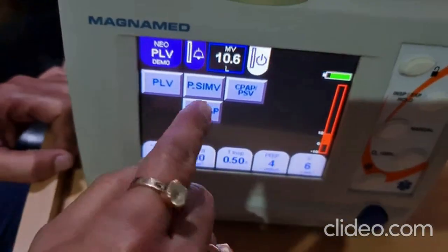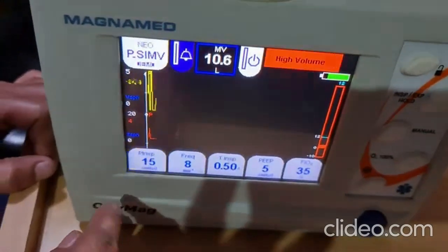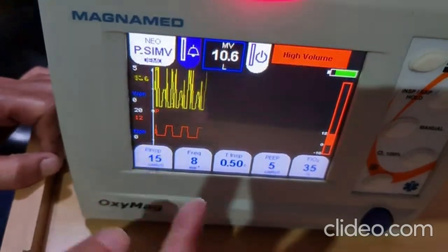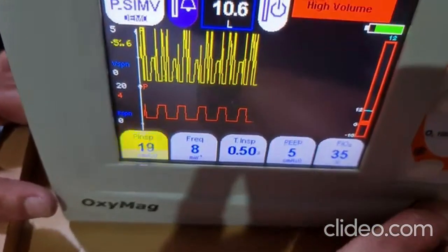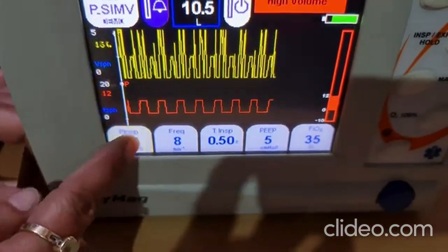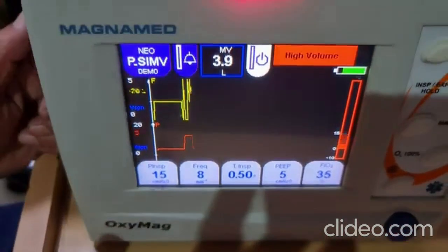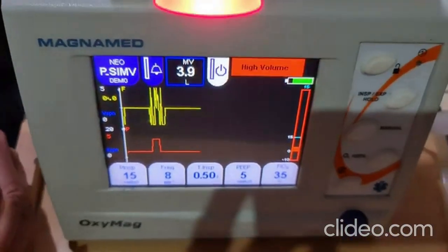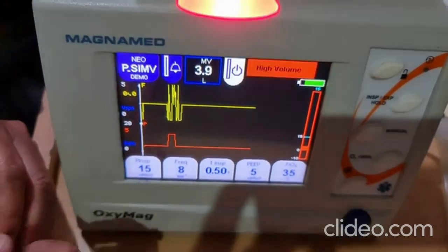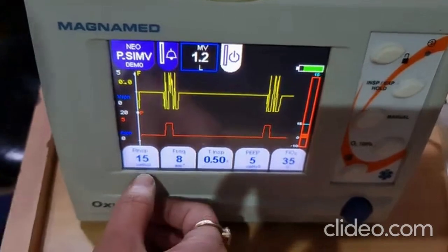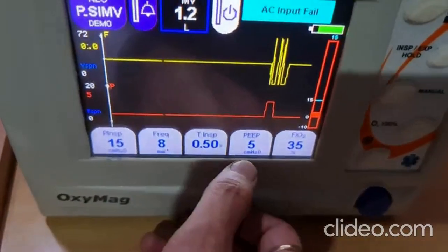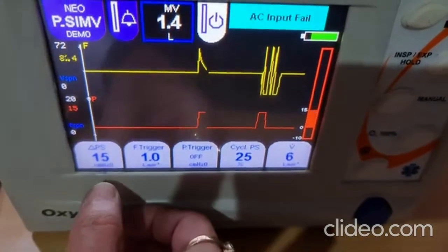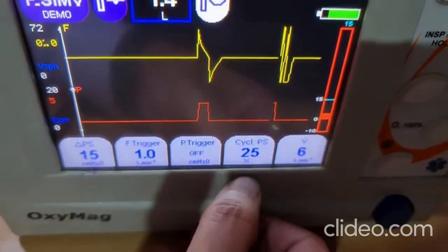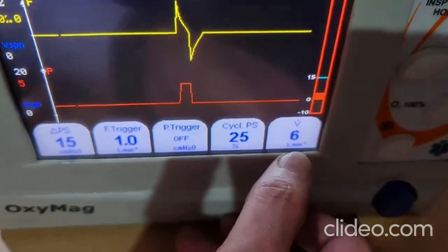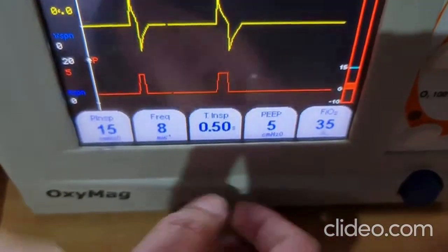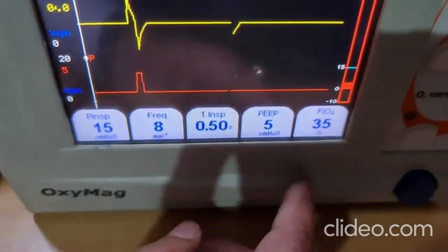If you want to change the mode, select this mode. It will blink. You have to confirm this if you want to change this blinking parameter, or you just confirm this to activate the next mode. If you will not confirm, it will come to the previous mode after few seconds. In this SIMV mode, you have inspiratory pressure, frequency, inspiratory time, PEEP, FiO2, and the next page is pressure support, flow trigger, pressure trigger, cycle pressure support, and the flow. These are the set parameters.